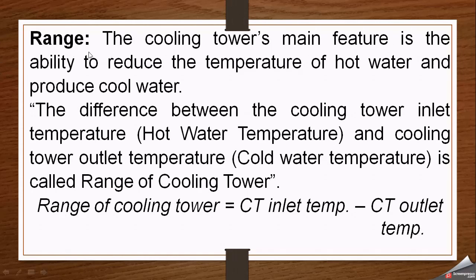Another important term is range. The cooling tower's main feature is the ability to reduce the temperature of hot water and produce cool water that can be recirculated back to the system to absorb heat and return to the cooling tower. The difference between the cooling tower inlet temperature — the hot water coming from the process — and the cooling tower outlet temperature — the cold water obtained after passing through the tower — is called the range. Range = cooling tower inlet temperature minus cooling tower outlet temperature.